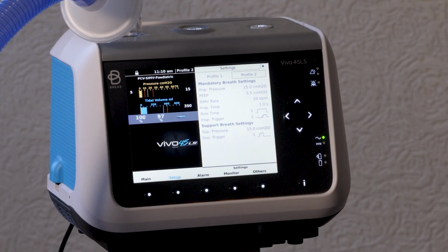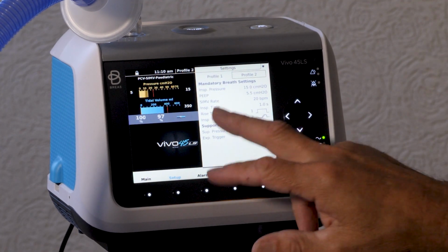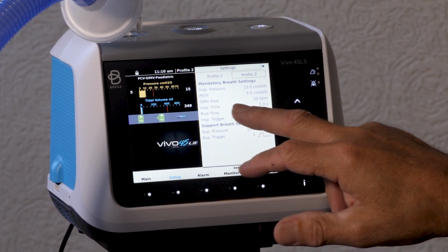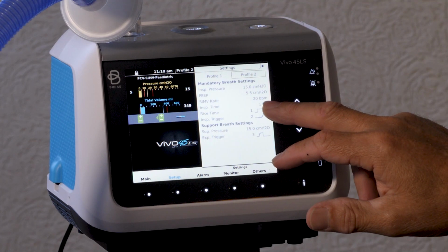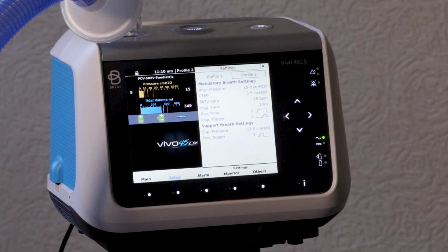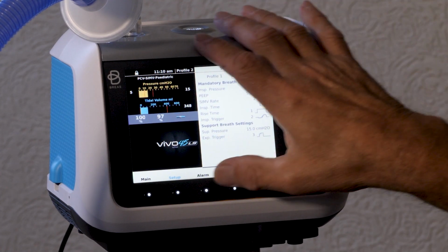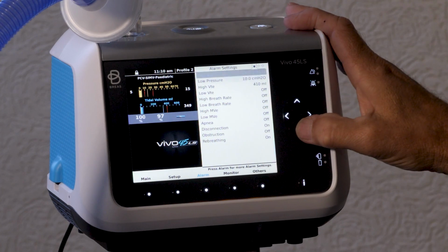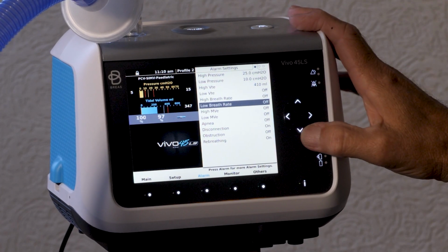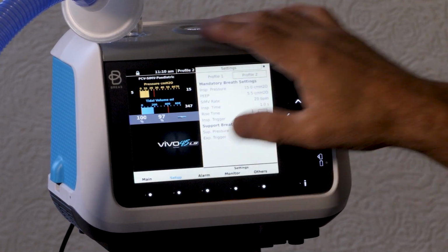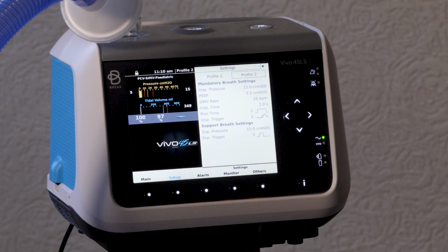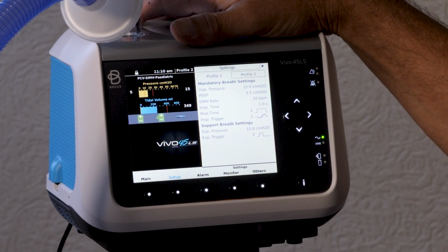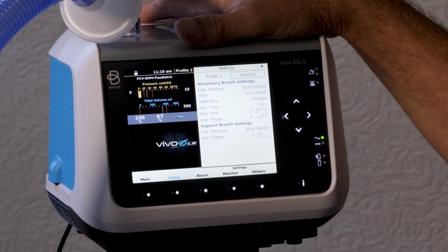And if you hit the setup button, like I just did here, and you go to where it says rate, then that's the prescribed minimum amount of breaths that the patient should be receiving. So if I set the low breath rate alarm to, let's say, 18, and I'm supposed to be getting 20 breaths per minute, then I know that the ventilator is not giving what it's supposed to, the minimum amount of breaths it's supposed to be giving, so it's a ventilator problem.